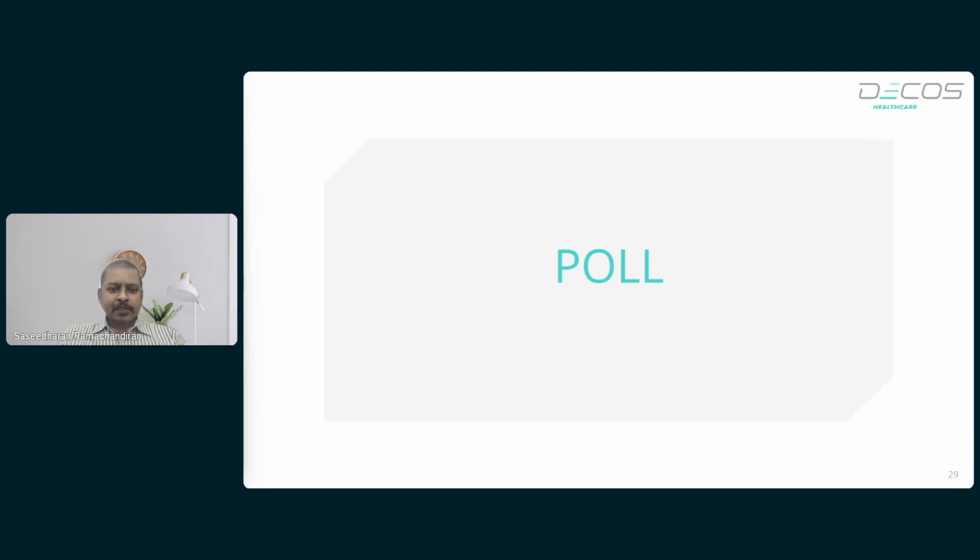Thank you for your participation. I could see most of the people have chosen the answer A. The correct answer is A, EU MDR, because the EU MDR imposes more stringent requirements for post market surveillance and vigilance for Class 3 devices compared to US FDA. This includes comprehensive monitoring processes, mandatory periodic safety update reports, and a more proactive approach to identifying and mitigating risk associated with these high-risk devices. This heightened level of oversight ensures safety and effectiveness in the market.